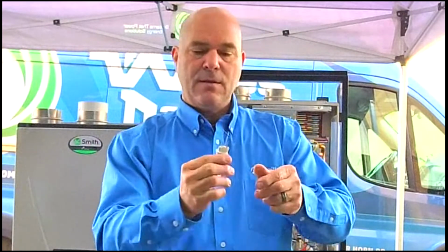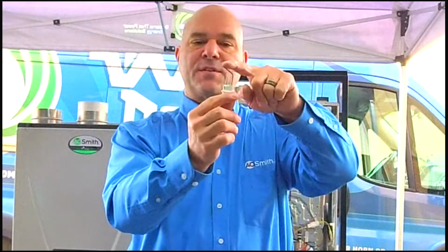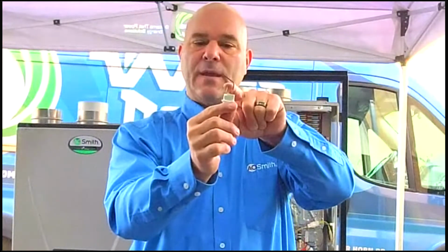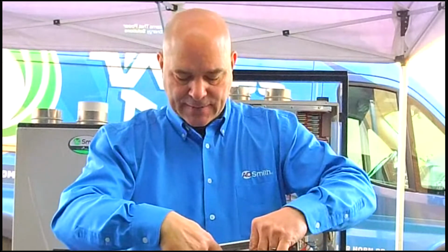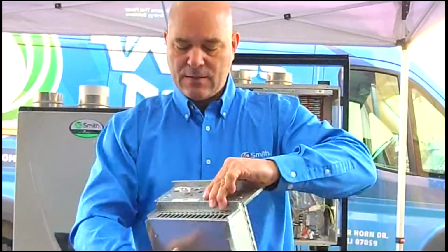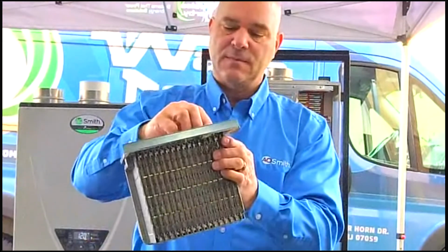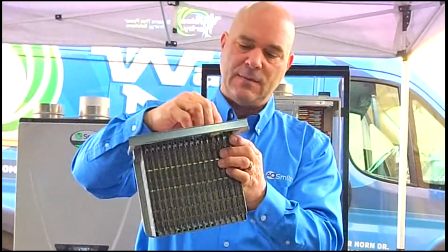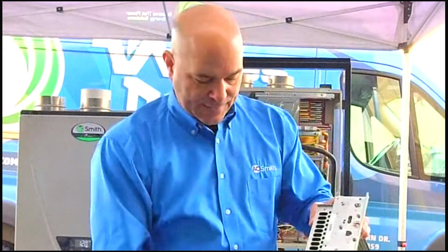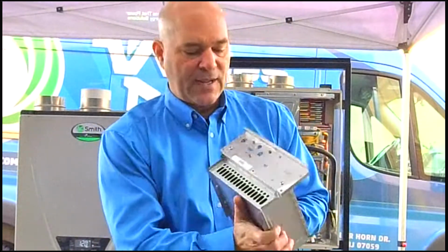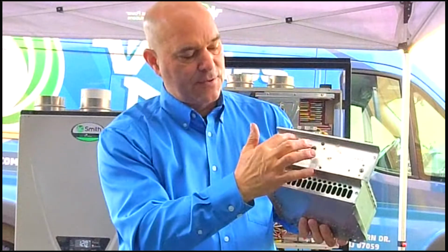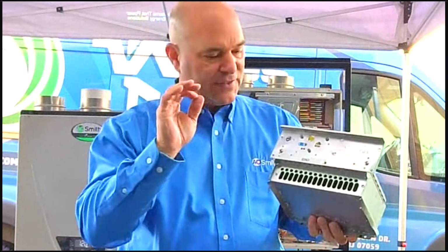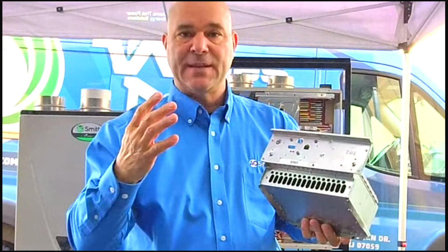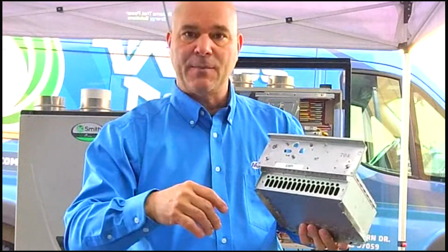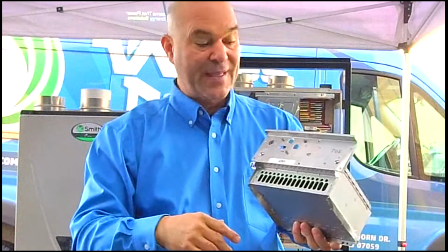This is the flame rod. The long one is the flame rod. The short one is the AFR, the air fuel ratio rod. They will insert directly into this position. And when it's in position, this is what it will look like when it's in. And again, that will babysit the flame. To take those out, there are three Phillips head screws. There's a white gasket behind there. If you're extremely careful with the gasket, it will stay together. If it tears, you'll have to end up with a new one. Do what you've got to do to make sure that it is sealed.